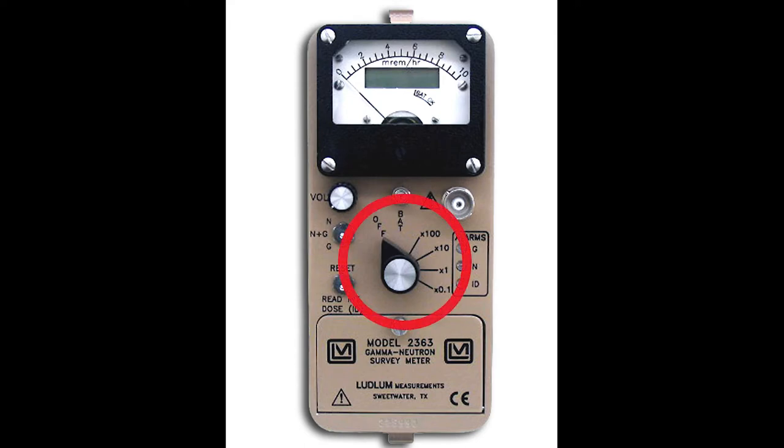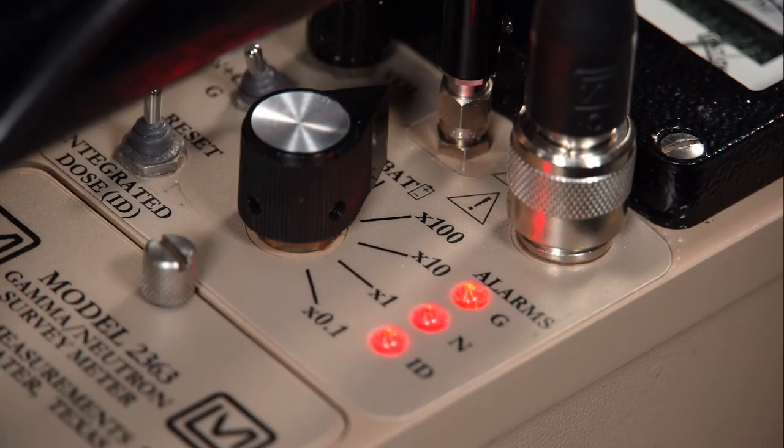The operator controls for the Model 2363 consist of a six-position rotary switch to select the analog meter range multipliers and check the battery status. When the switch is rotated to the bat position, the meter pointer should deflect above the left vertical mark.